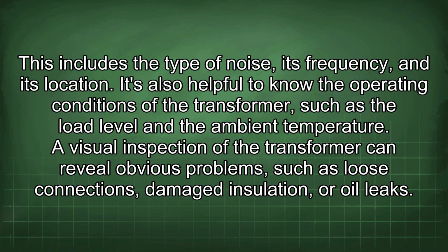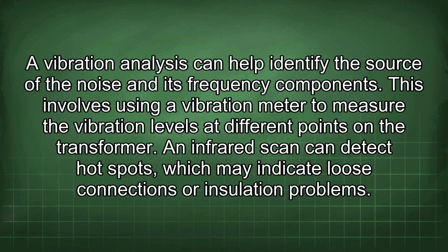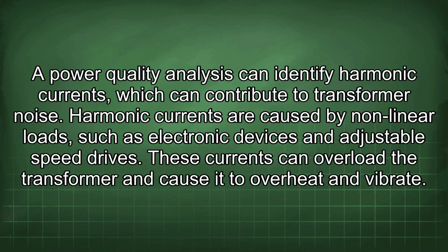A visual inspection of the transformer can reveal obvious problems such as loose connections, damaged insulation, or oil leaks. A vibration analysis can help identify the source of the noise and its frequency components. This involves using a vibration meter to measure the vibration levels at different points on the transformer. An infrared scan can detect hot spots, which may indicate loose connections or insulation problems. A power quality analysis can identify harmonic currents, which can contribute to transformer noise.